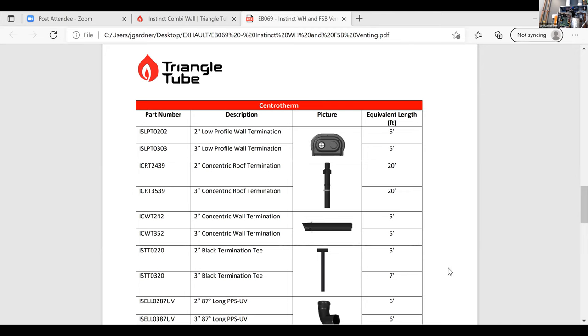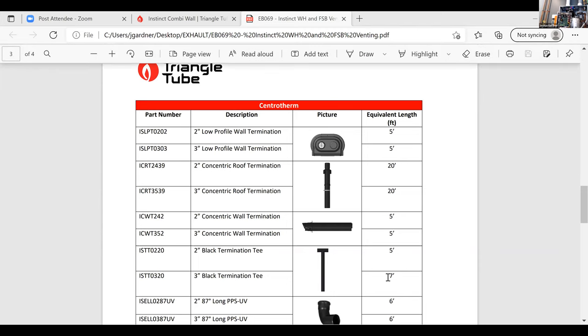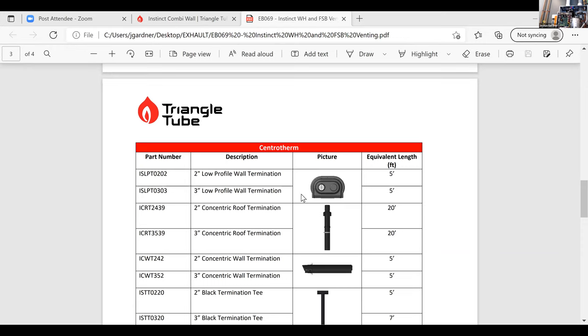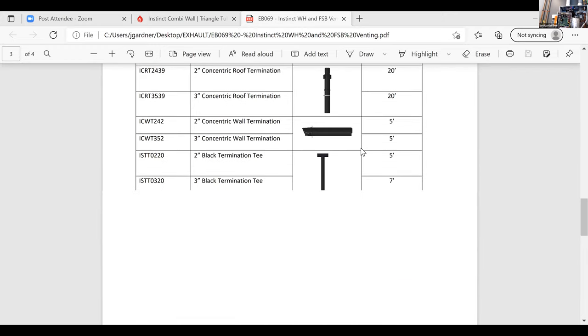Those kits were initially developed for through the roof penetrations, and they work well through those because the exhaust is higher than the intake. But at some point in the early 2000s, we started using them on sidewall because it was one penetration and they were really cheap. So those PVC bazooka kits, I would highly recommend staying away from. Try to find a concentric kit if you're going to use one that has your intake on the bottom. Okay, those typically use the best.